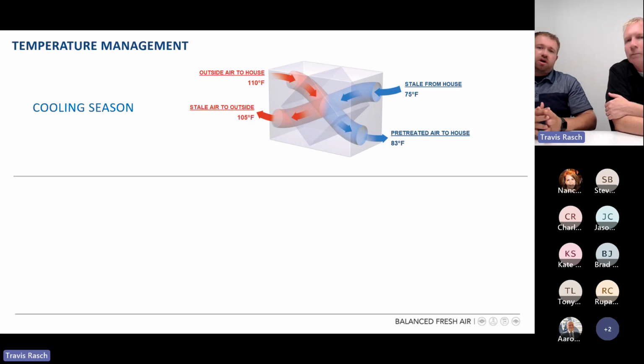As an example here, this is simply temperature: we have an outdoor condition of 110 degrees Fahrenheit, and we've cooled our air in the house to 75 degrees. Those two air streams pass through that recovery core, and based on the efficiency of this core, we can expect that 110 degree outdoor air coming into our home gets filtered and tempered, and we deliver 83 degrees Fahrenheit tempered air to the house, whether directly to the home or to the air handler.